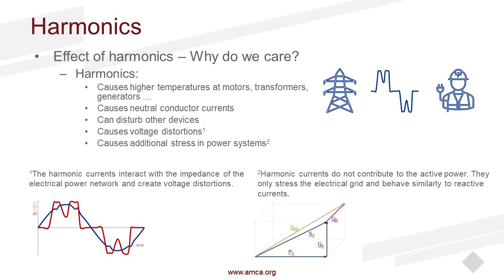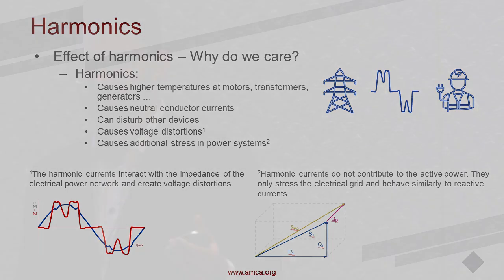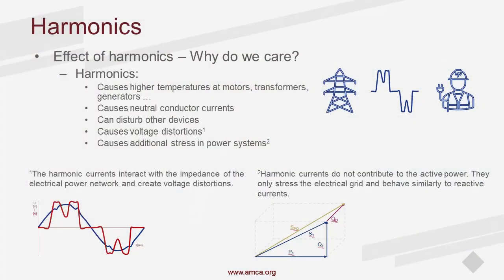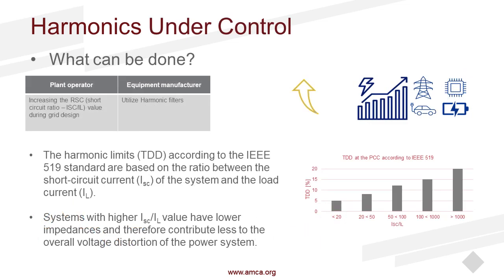So this relationship is what's giving you your power factor, so how efficient your system is running. And when you add harmonics to your system, it's like adding more foam. So now you have less beer. We don't want that. So this is the stress that's put on your power grid. So what can be done? On the equipment side, we can look at different filtration options, and we'll get into that a little bit later.